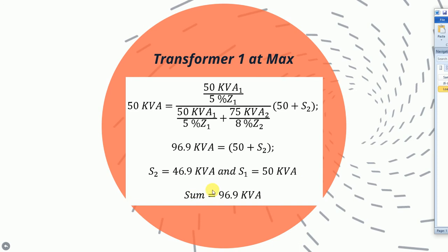Transformer 1 is within its rated capacity and Transformer 2 is also within its rated capacity. This is going to be the answer, because as we add more load to the parallel set of transformers, they will load proportionally to this ratio. Although Transformer 2 can take more capacity, Transformer 1 will be unable to take more capacity.